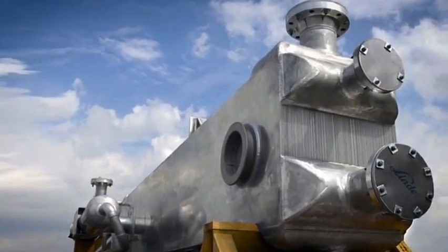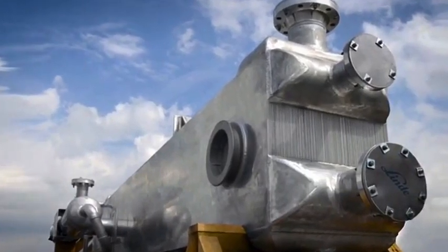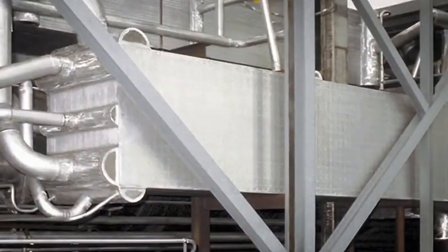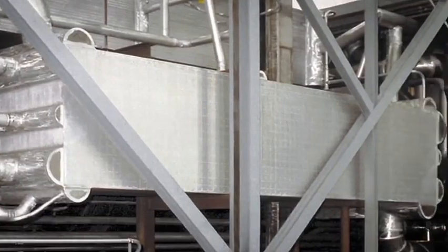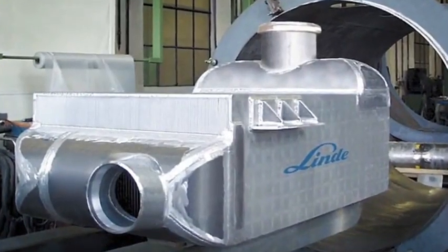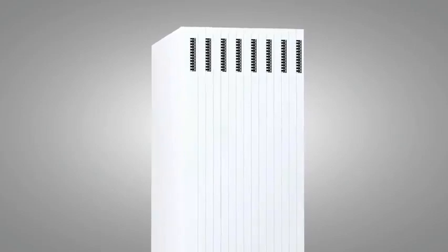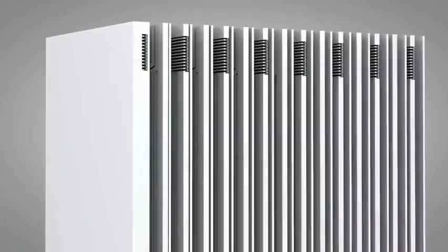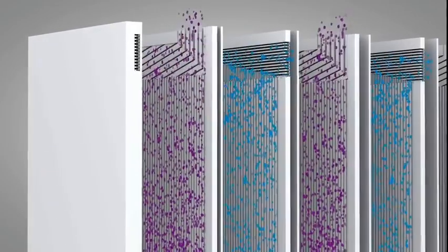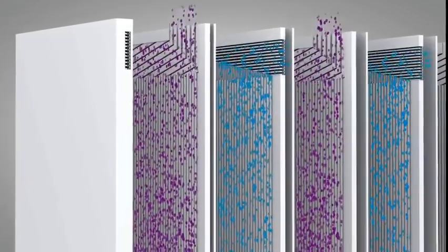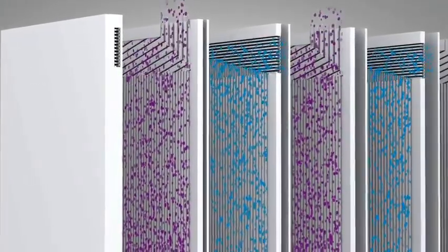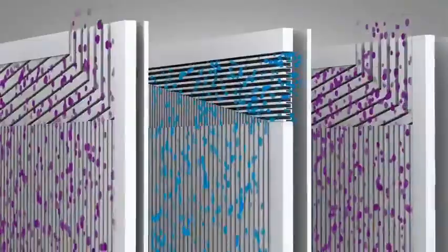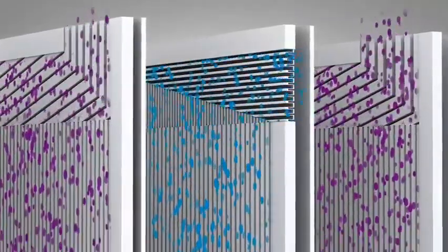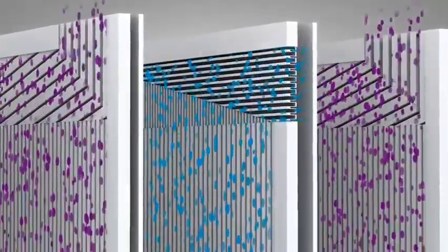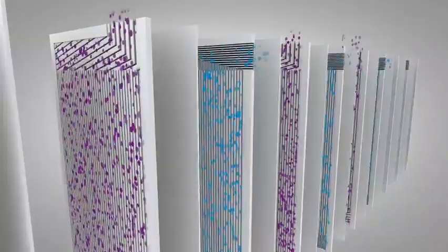The other widely used LNG exchanger is the plate-fin type. They're smaller and lighter than coil-wound exchangers, and we can easily scale them from small to large sizes. A look inside shows how it works: fluids move through alternating layers of corrugated fins separated by flat plates, transferring heat between natural gas and refrigerants. Those fins enhance heat transfer from the fluid, and they conduct more heat directly into the plates.